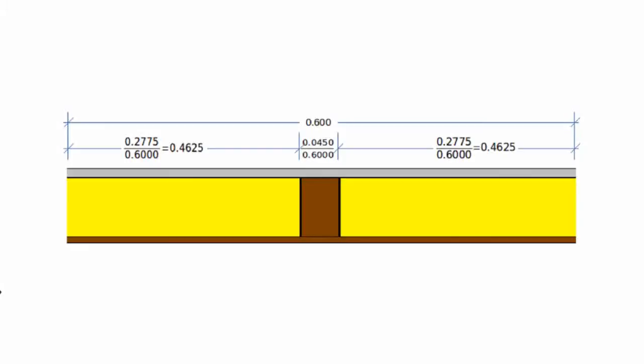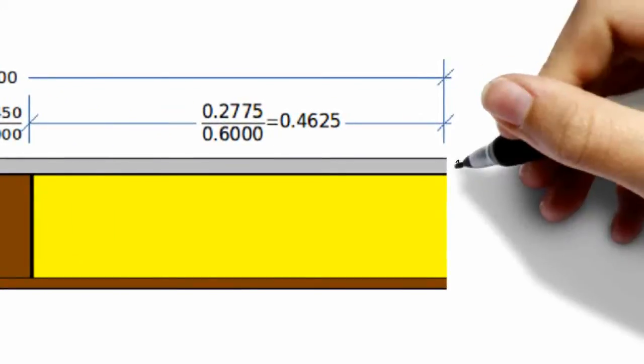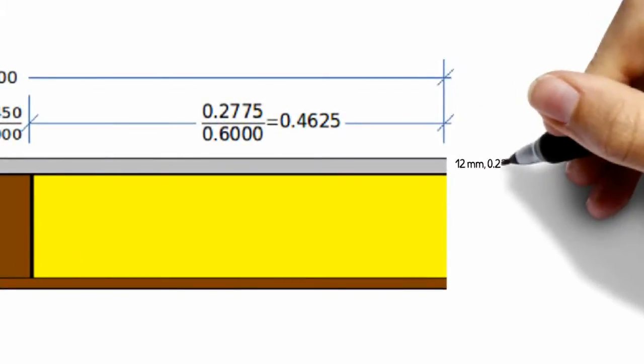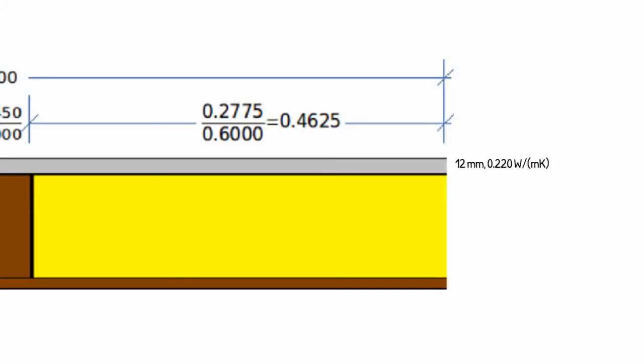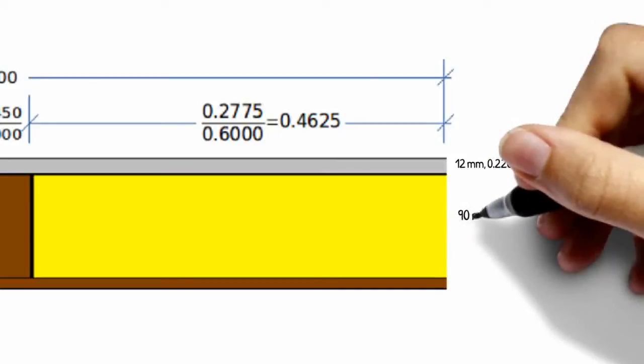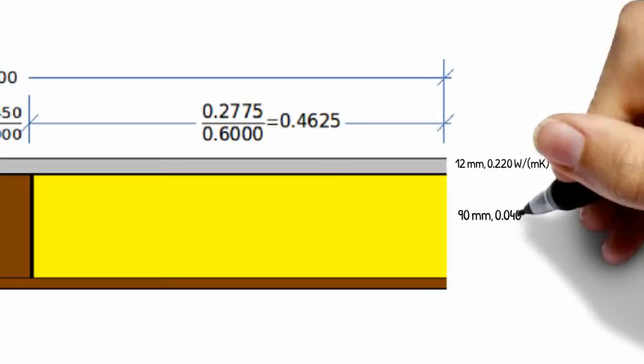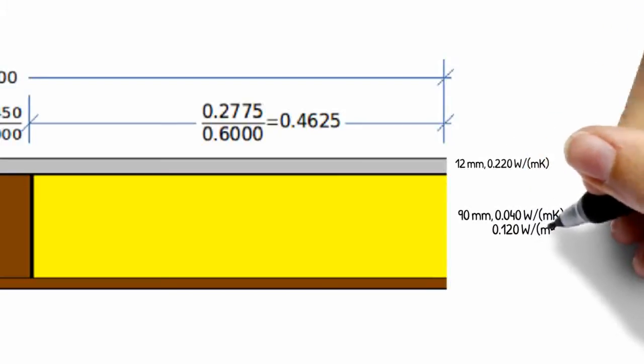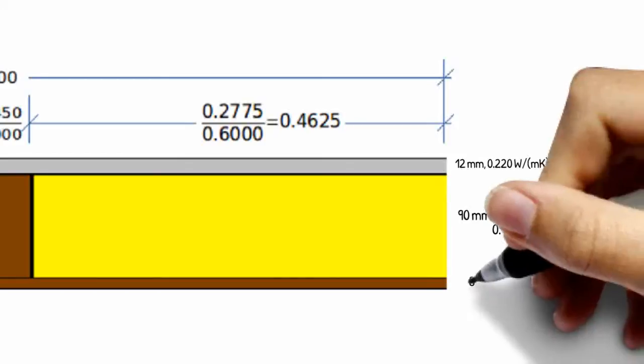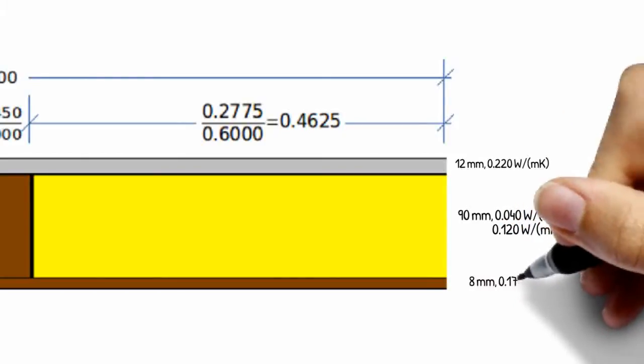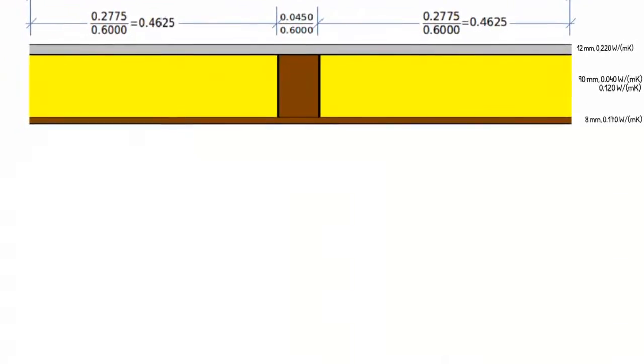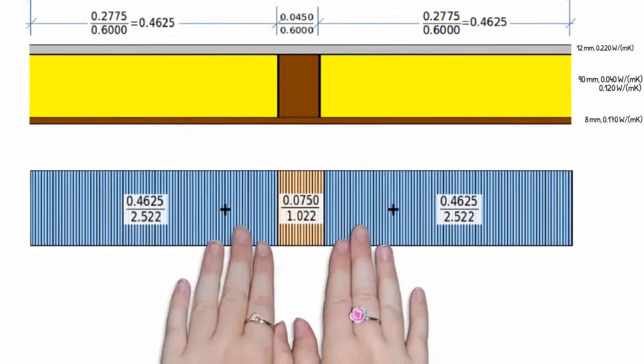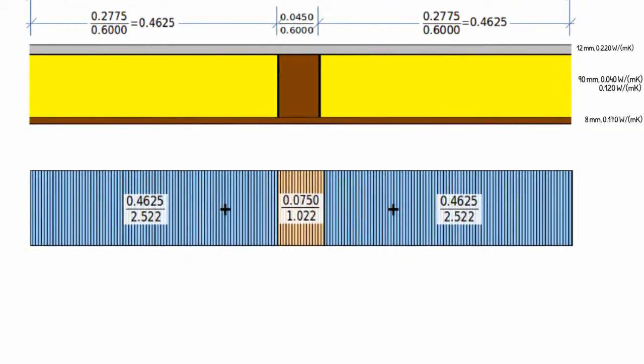Let's assume the timber wall we're interested in has a timber stud at 60 centimeter centers. Here's our plasterboard and its thermal conductivity, then the insulation and the thermal conductivity, and in the same layer the softwood stud and its thermal conductivity. Let's assume we have a plywood rigid air barrier on the outside, 8 millimeters, thermal conductivity 0.110 watt per meter kelvin.